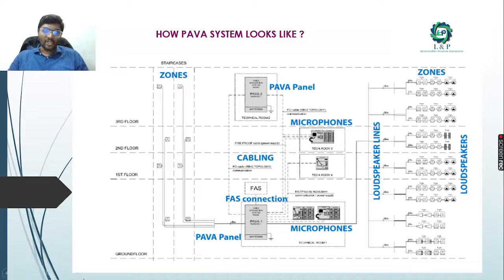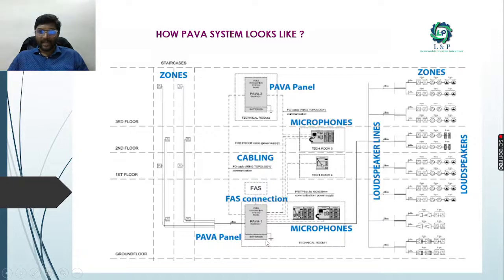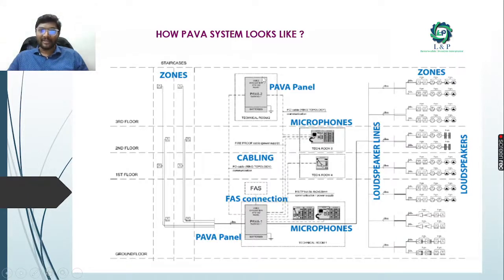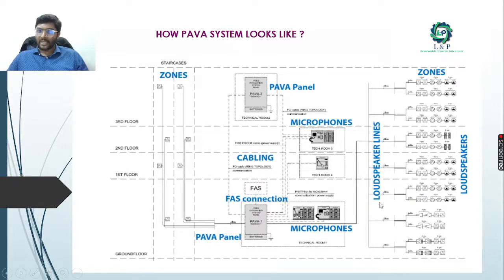An example system architecture for a three-floor building: ground floor, first floor, second floor, and third floor with many zones. A fire alarm system connects to the PAVA main panel, with batteries for power supply. Microphones from different floors connect to the PAVA panels - even the third floor has a PAVA panel. With multiple panels, one is the master and others are slaves. Based on the number of I/O connections and voltages, speakers connect to the entire system through loudspeaker lines on different floors.